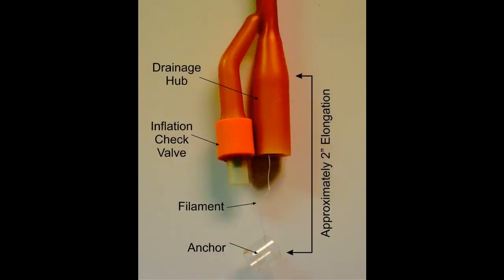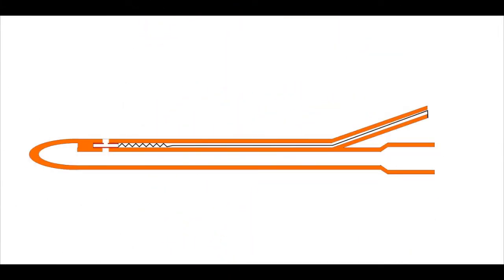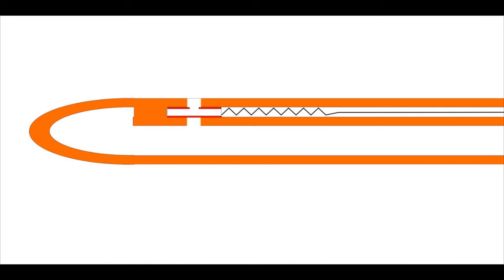Let's revisit the length of the filament from the anchor to the catheter. If you make this larger, say 7 inches, the catheter will elongate about 50% before the valve is pulled downward and balloon deflated. Alternatively, the stretch valve can be placed in the inflation lumen. Here is a close-up of the stretch valve in the inflation lumen.